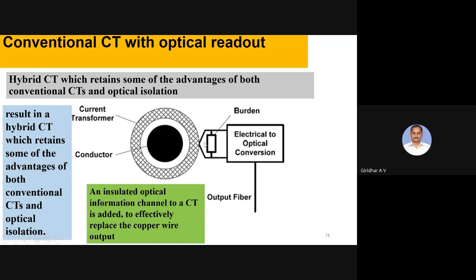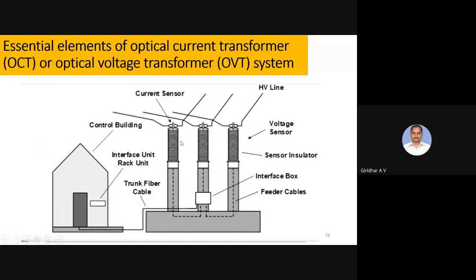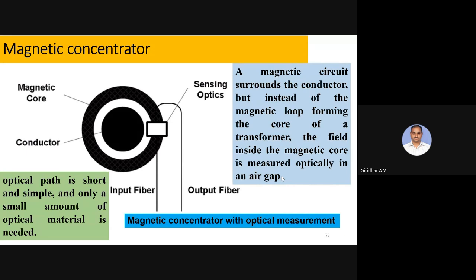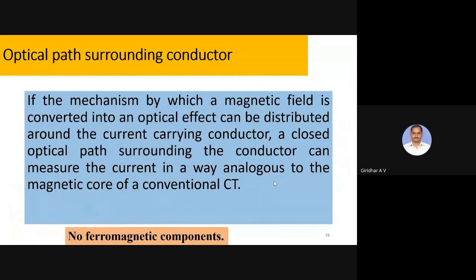So these are the conventional CTs with optical readouts. In that way, in the current transformer aspect also, there are more advances. You can see the electrical to optical conversion unit from the current transformer to here. With the conventional CT with optical readout, this is one type of device. You can see an optical current transformer or optical voltage transformer in this, with the magnetic concentrator and optical measurements. In that way, we can use IoT for these measurements and take appropriate actions also. The optical path.